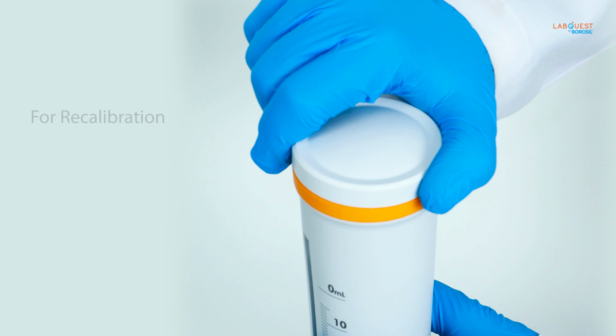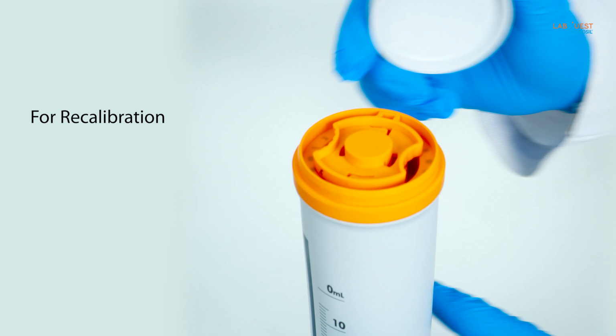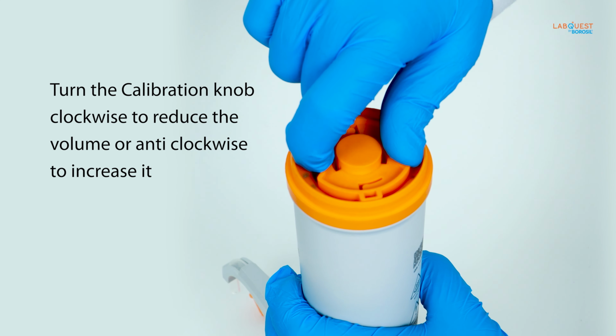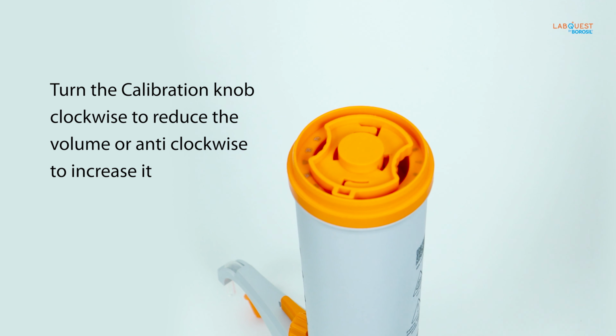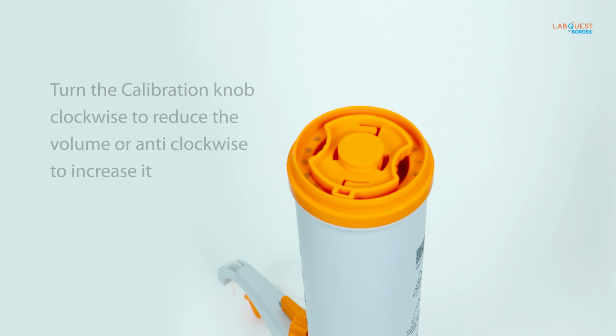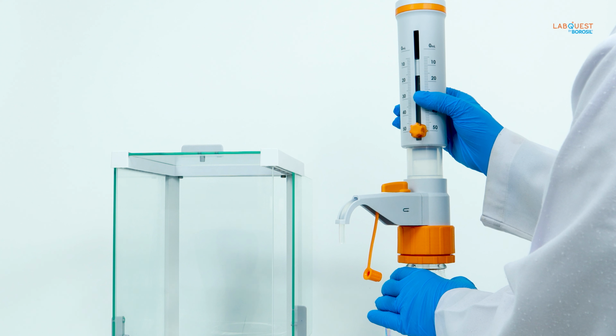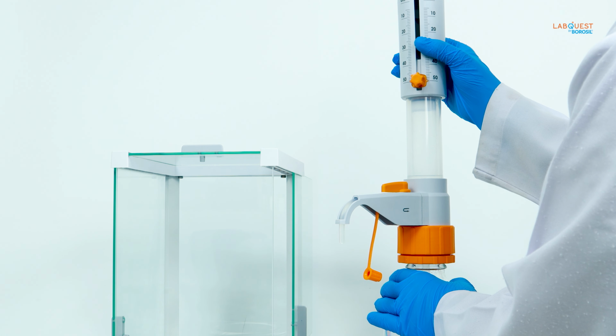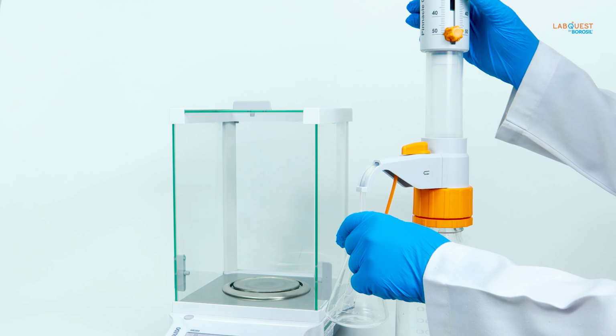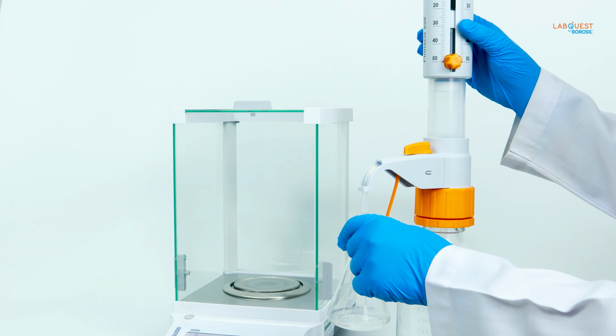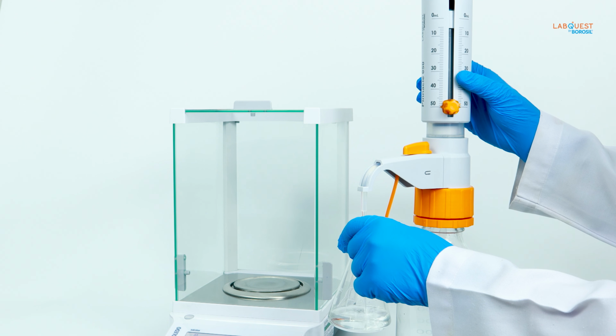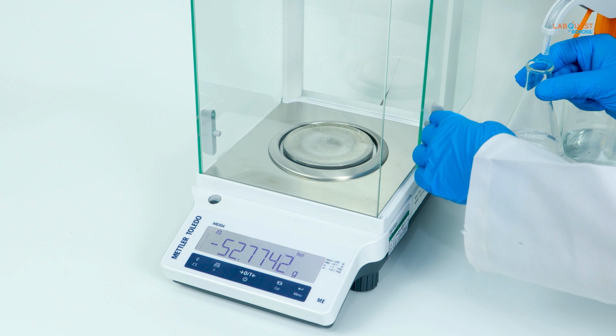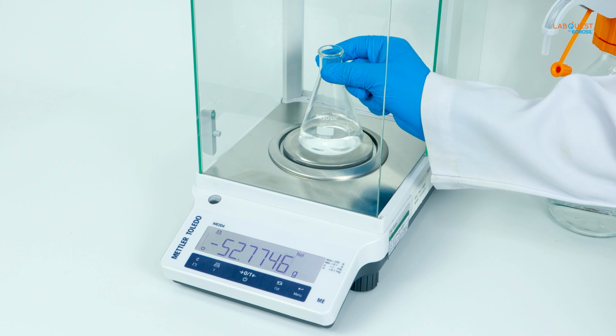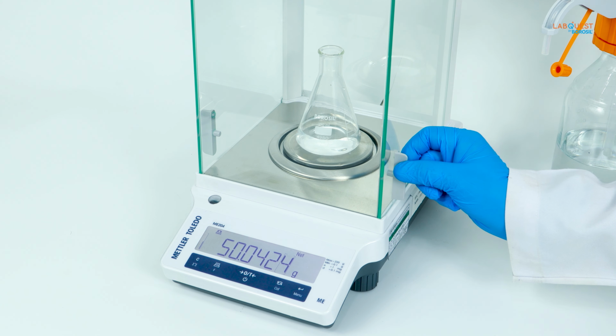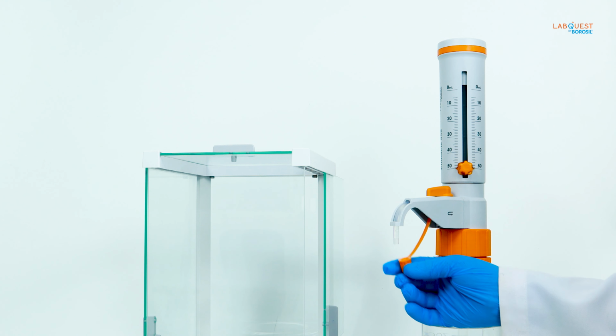For recalibration, remove the safety cap. You will see the calibration ring. To fine-tune the calibration, turn the calibration knob clockwise to reduce the volume or counterclockwise to increase it. Keep repeating this adjustment process until you reach the desired volume as displayed on the electronic balance. After successfully calibrating the instrument, remember to reattach the safety cap.